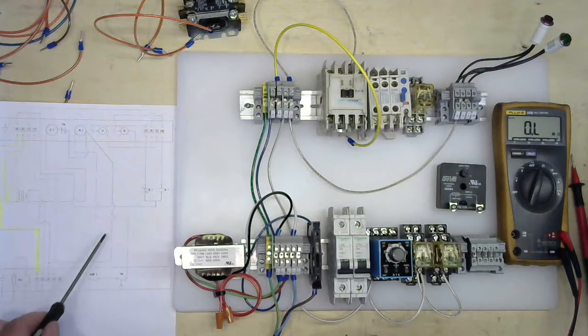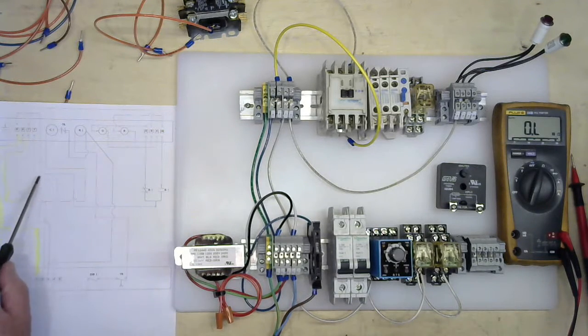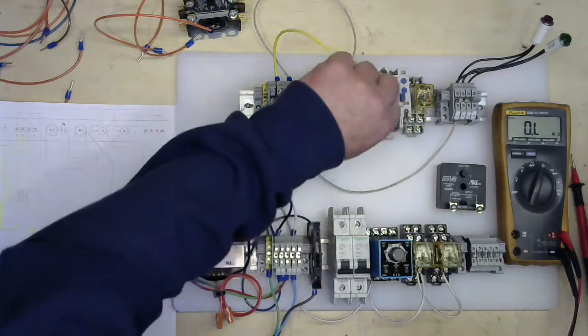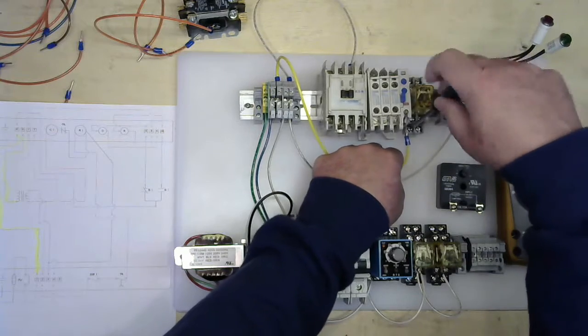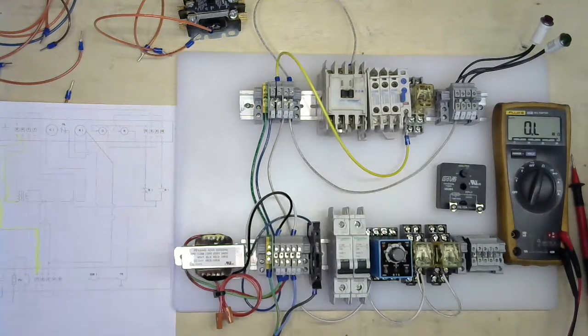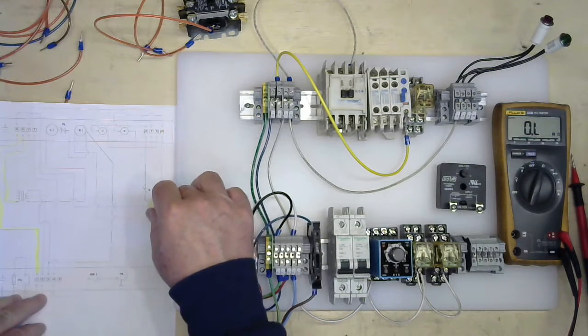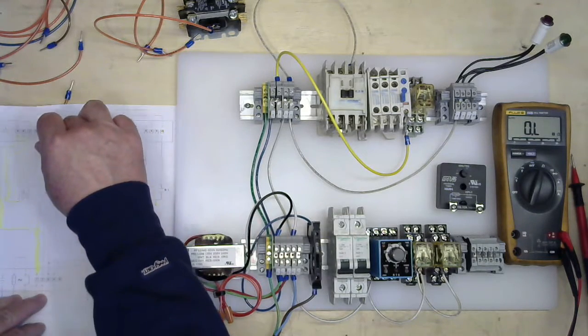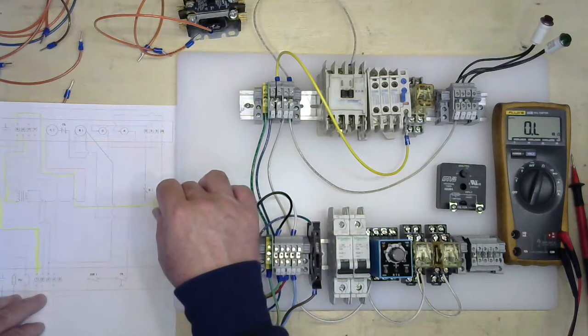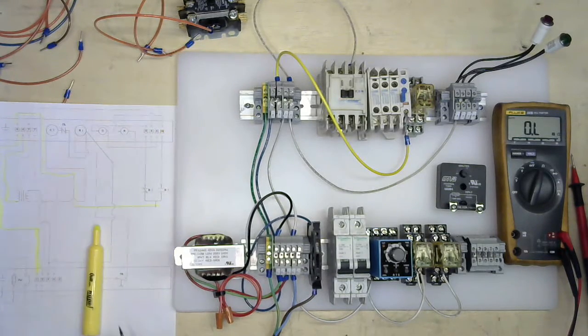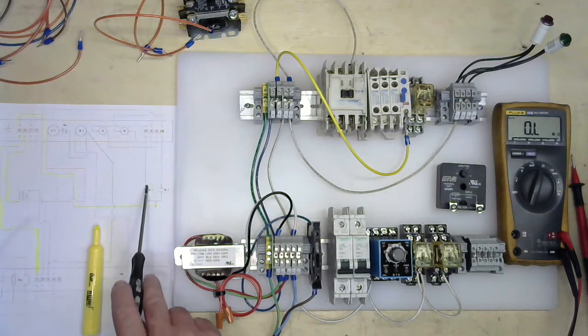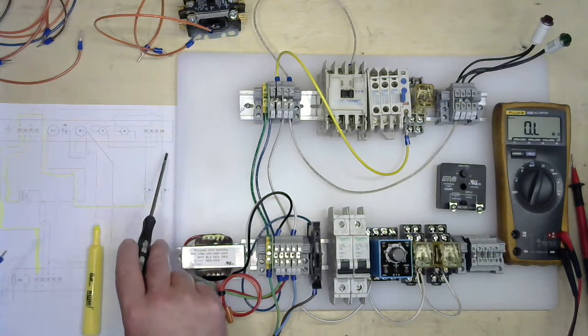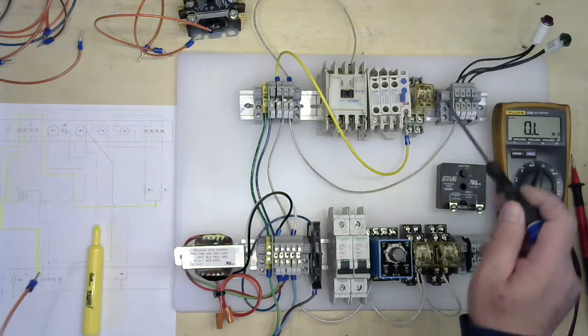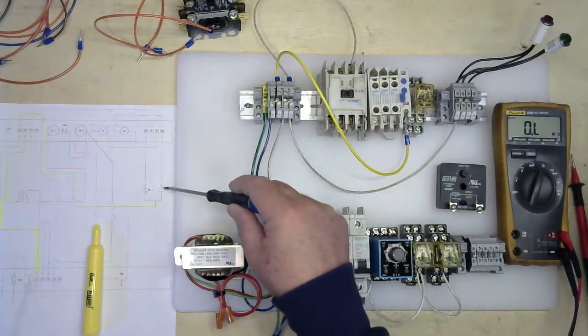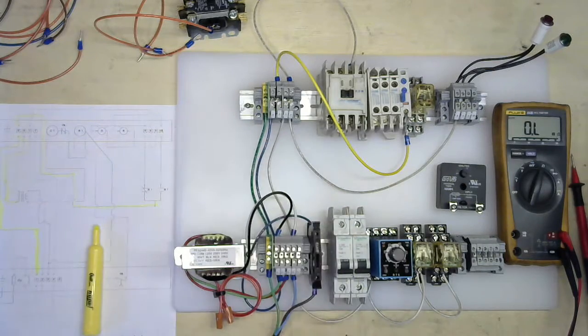So according to my diagram, I want to go from 6 to my common, which is going to be here on the bottom. And tighten that down, pull on it, and now I am going to be able to highlight this, saying that I've already gone to my common terminal. Now, since we're on board with this, let's go from our normally closed and our normally open terminals to terminals 8 and 10. Because my normally open terminal is on the back, I'm going to do that one first. So my normally open one is going to connect to terminal 10.